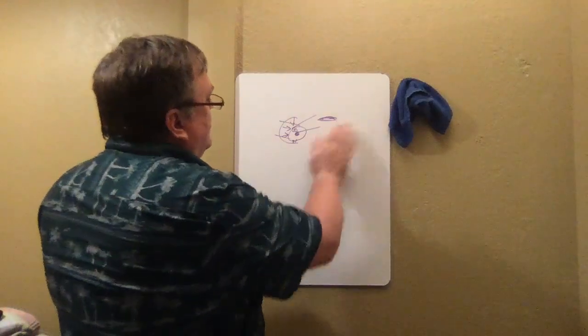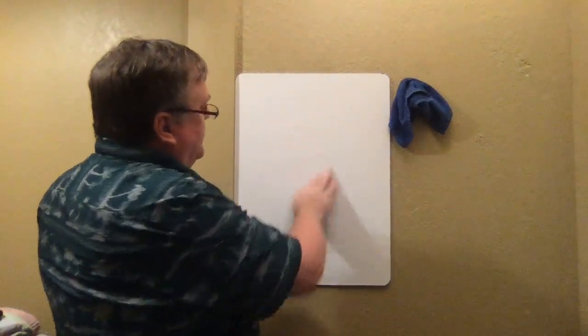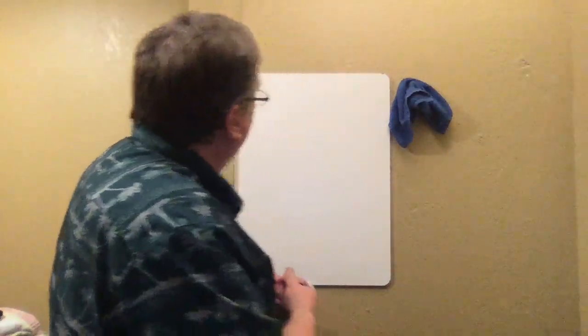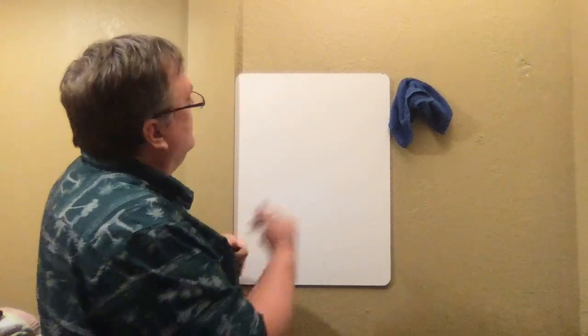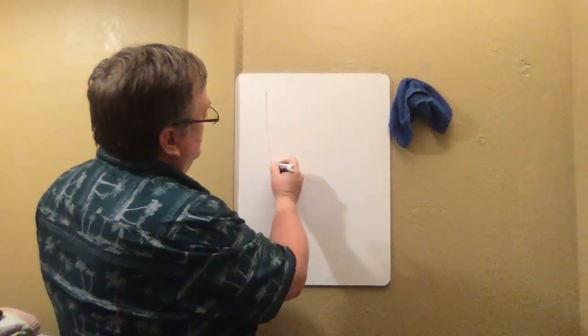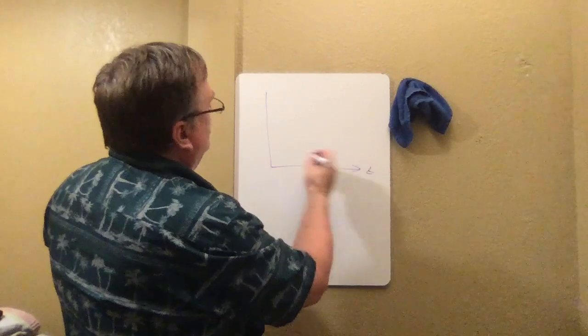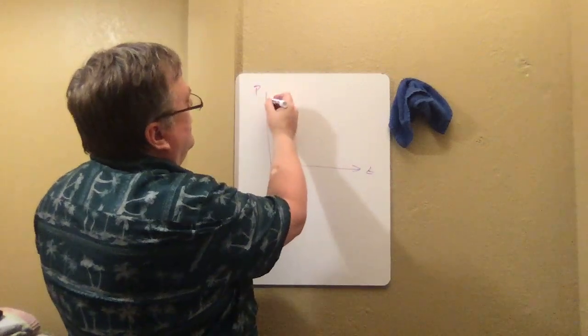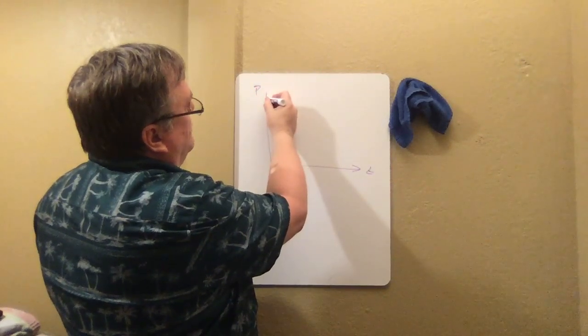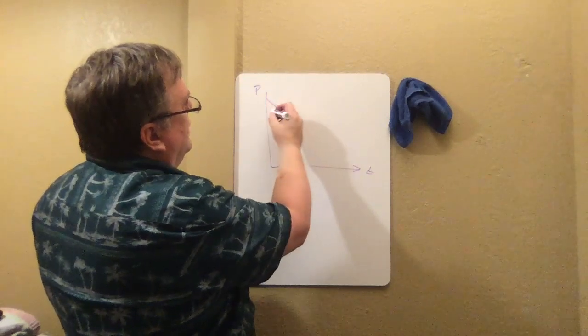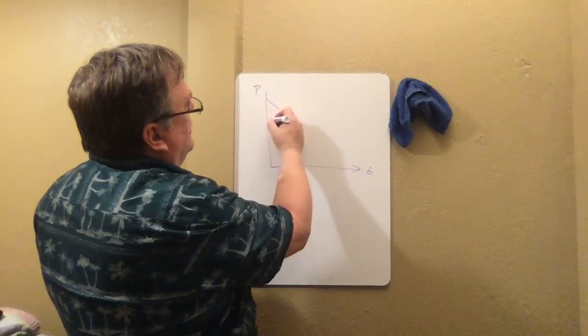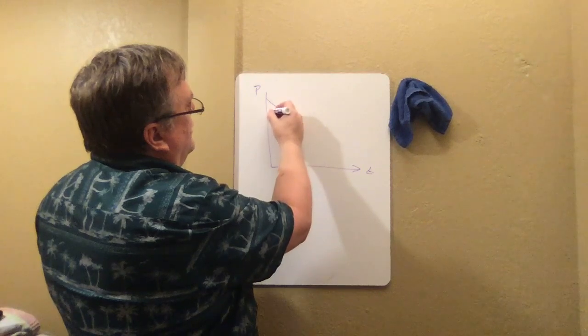In any case, that gives you the idea of squeezing them off. So we're going to measure them when it comes down. You want to put the cuff about the same level as the heart. This is important because you don't want a pressure differential caused by gravity to change what's going on here. And then so this is time, and you measure pressure. The pressure is going to come down, and somewhere around here, you're going to see the actual pressure wave.